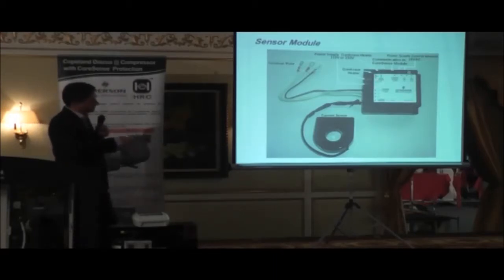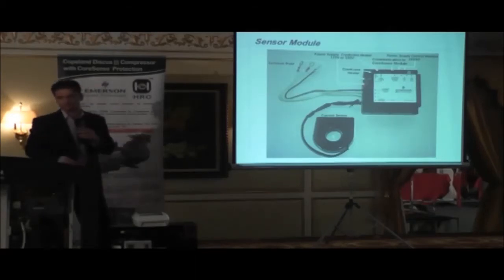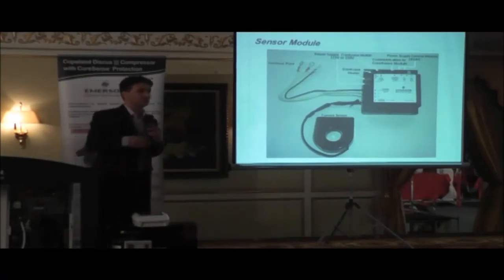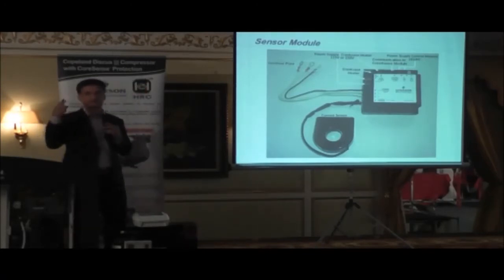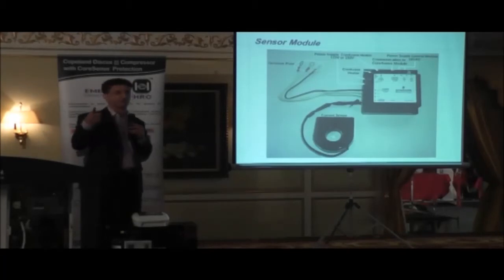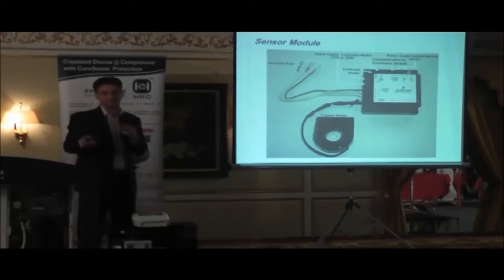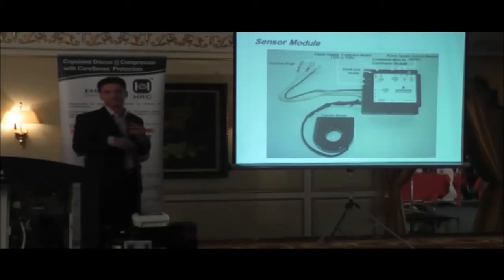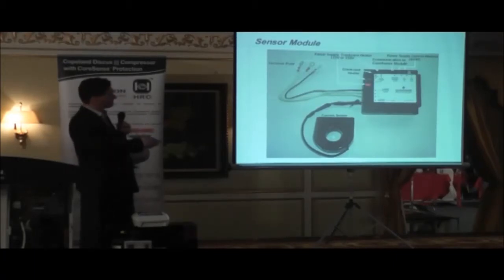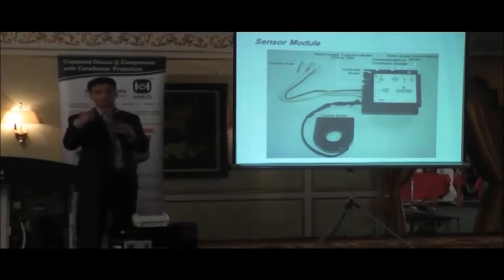We've also included a relay for the crankcase heater. Right. So if you were installing crankcase heaters on your systems, you would normally wire the supply to your crankcase heater through an auxiliary on your contactor, so that whenever the compressor switches off, you energize the heater. You do not need to do that anymore. This will be done automatically. So you just bring in your supply, connect your crankcase heater, and the sensor module will control the on and off of the crankcase heater automatically.